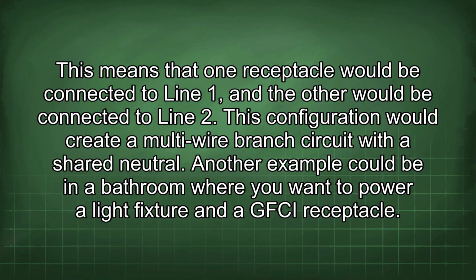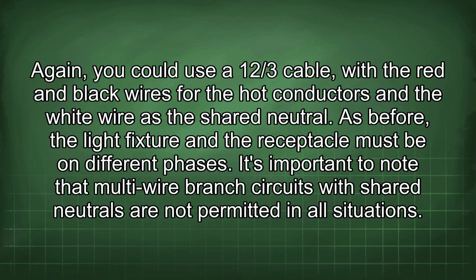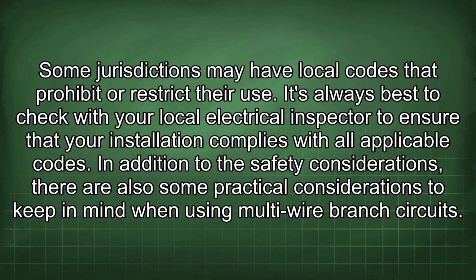Another example could be in a bathroom where you want to power a light fixture and a GFCI receptacle. Again, you could use a 12/3 cable with the red and black wires for the hot conductors and the white wire as the shared neutral. As before, the light fixture and the receptacle must be on different phases. It's important to note that multi-wire branch circuits with shared neutrals are not permitted in all situations. Some jurisdictions may have local codes that prohibit or restrict their use. It's always best to check with your local electrical inspector to ensure that your installation complies with all applicable codes.